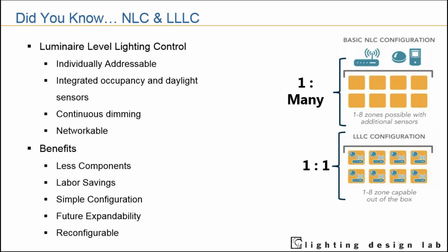As shown in this short animation, LLLC devices automatically meet code. They also need to provide continuous dimming—if you're still leveraging bi-level switching, we need a separate conversation—and ultimately they need to be networkable. Networkable doesn't mean every device has an IP address; it means there's an easy way to communicate with the device to reconfigure its settings.